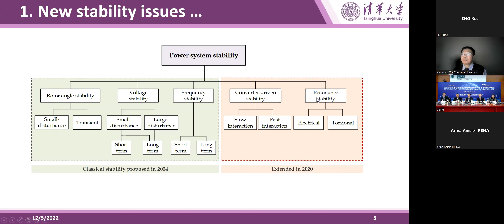We have also classified stability of new power systems from a different perspective. Here, power system stability is broadly divided into fundamental component stability and non-fundamental component stability. Fundamental component stability means the ability to maintain stable operation around the nominal frequency, that is 50 or 60 Hertz for AC and 0 Hertz for DC systems. Non-fundamental component stability is the system's ability to avoid or resist unwanted non-fundamental electromagnetic oscillation components.